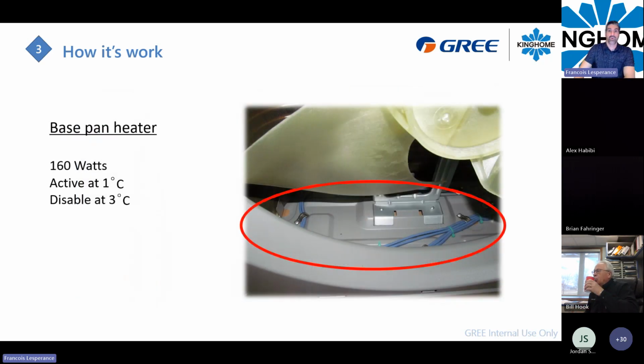The heat pump is equipped with a base pan heater. This heater in the base pan is active at 1 degree Celsius, and it will be disabled at 3 degrees Celsius. What it's meant for is to avoid ice building up in the pan. You will have some holes in the pan to evacuate all the water from the defrost cycle, and the heater is just to prevent ice buildup that can block the condenser fan.